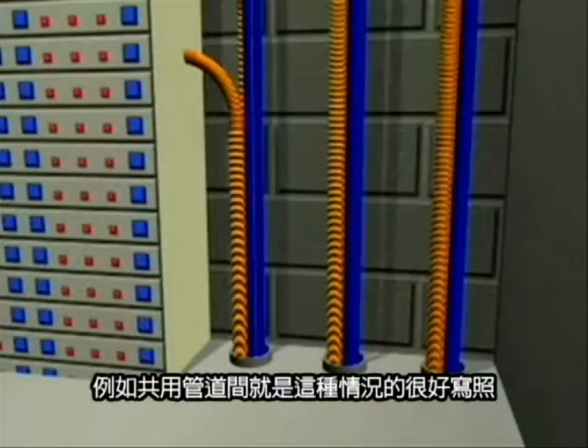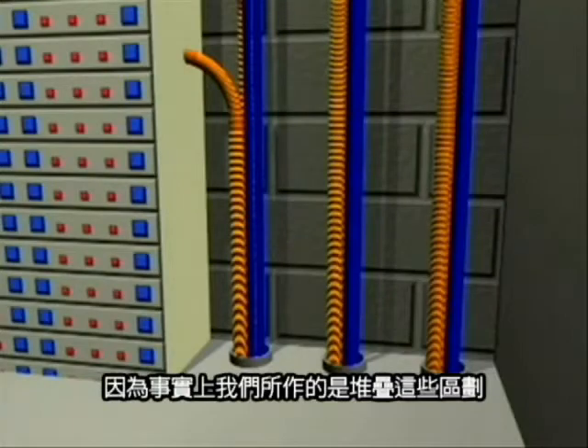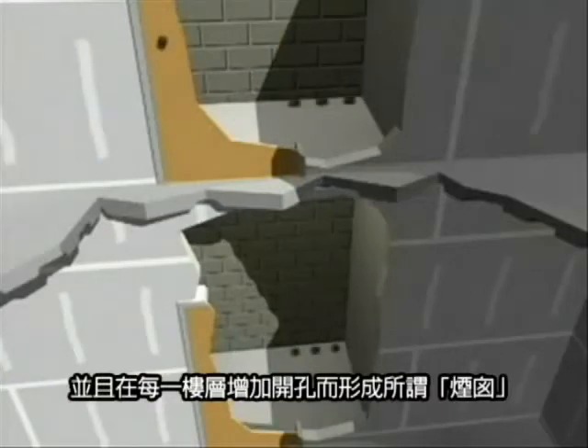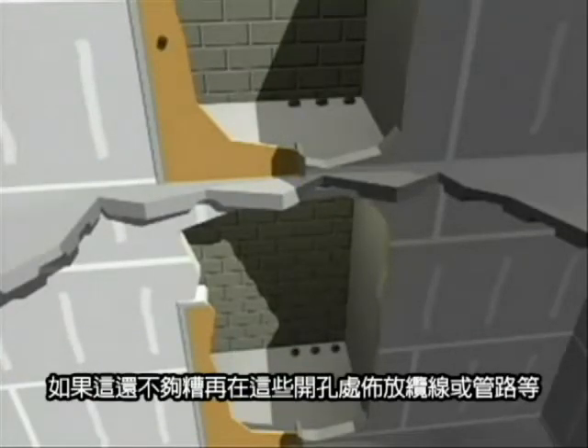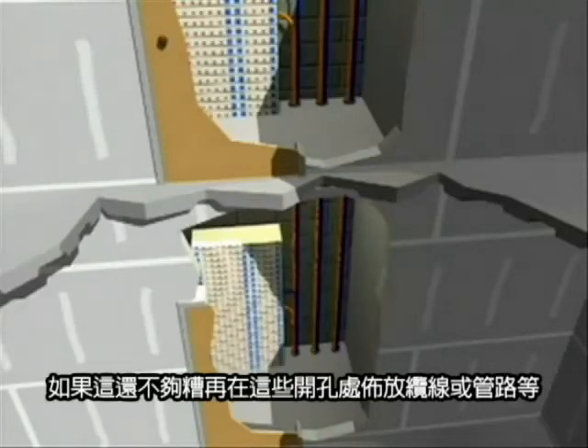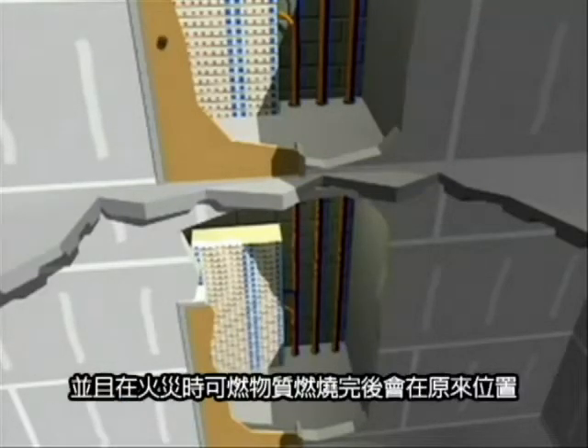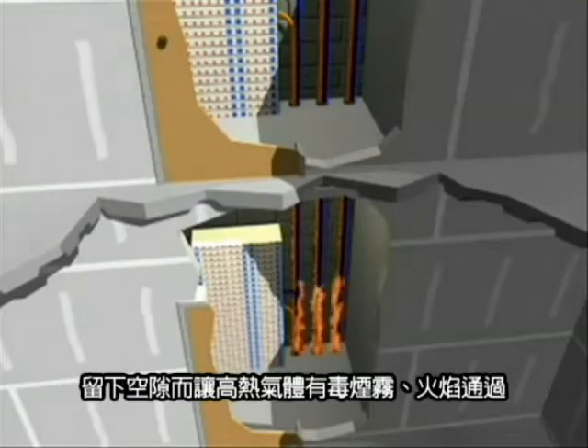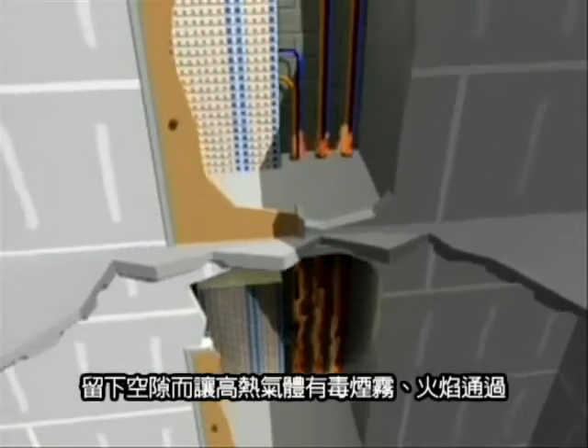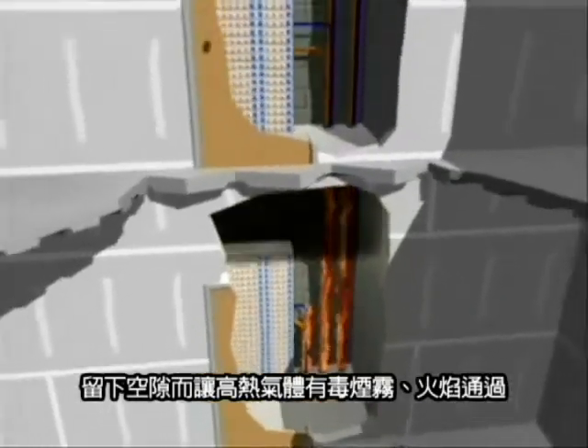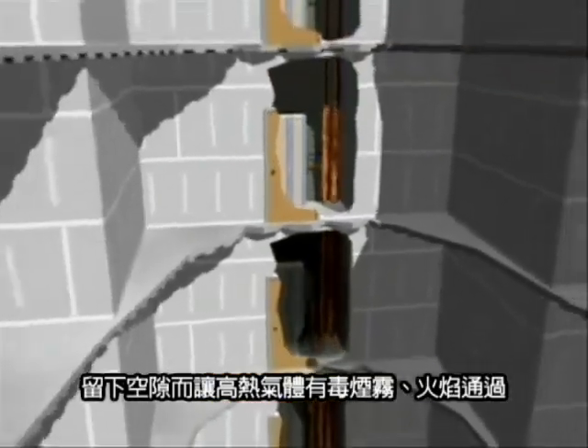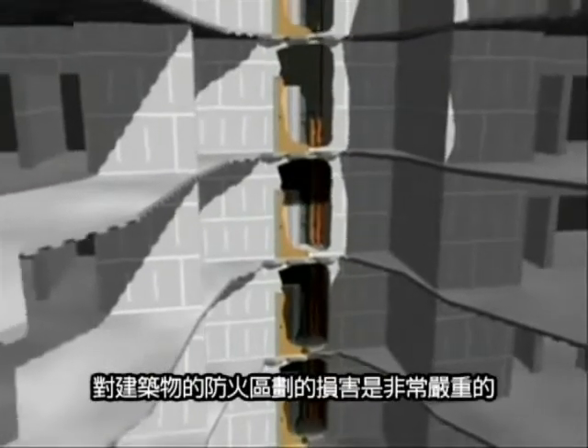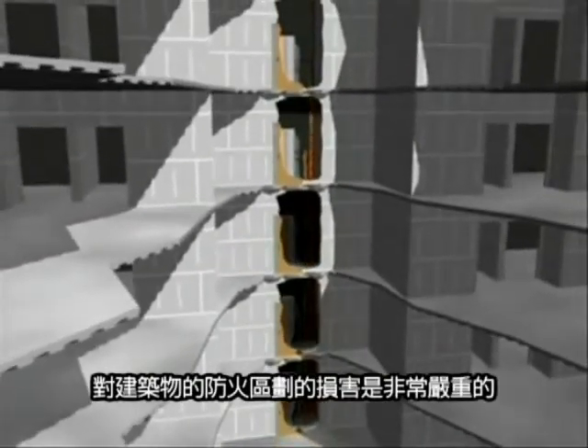Utility closets illustrate the point well because, in effect, what we are doing is stacking these compartments and adding openings in each floor, creating a chimney. If that weren't bad enough, we then load these openings with cable or fuel. And during a fire, the combustible materials are consumed, creating a gap in their absence that permits the passage of superheated gases, toxic smoke, flames, and heat. Needless to say, this seriously jeopardizes a building's compartmentation.